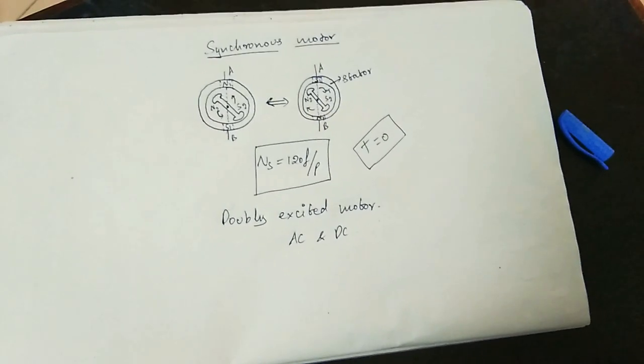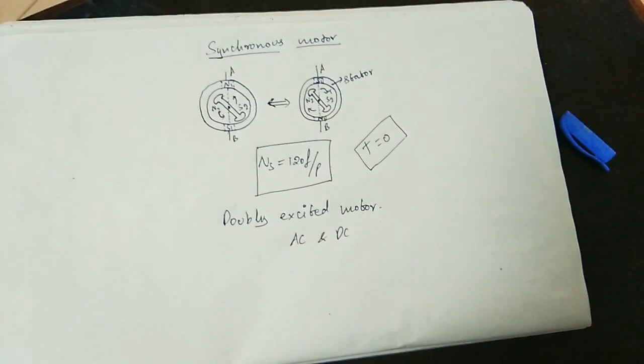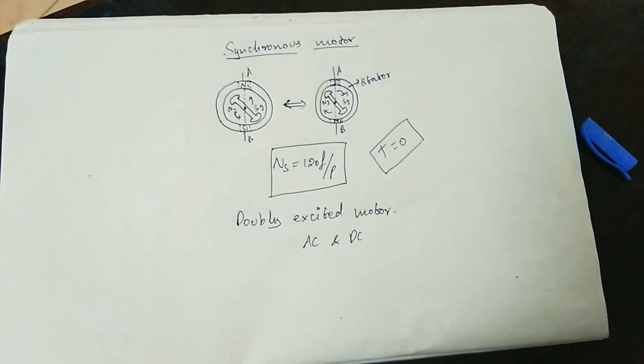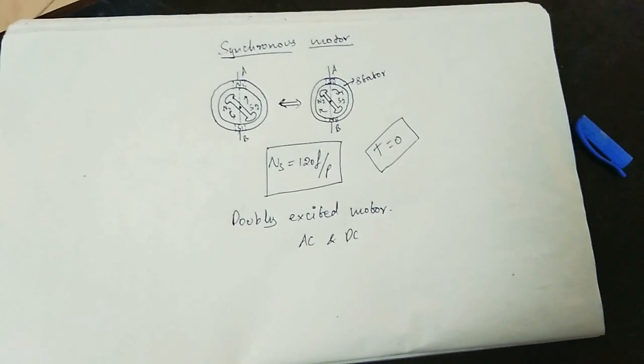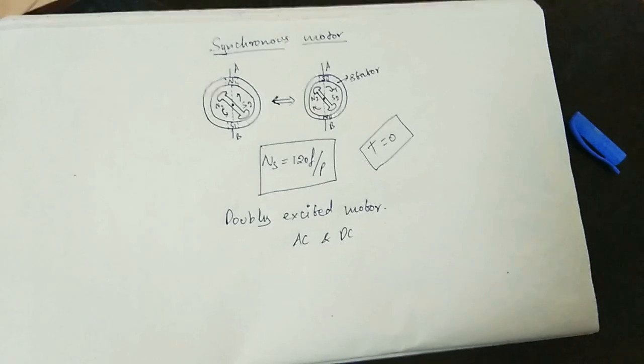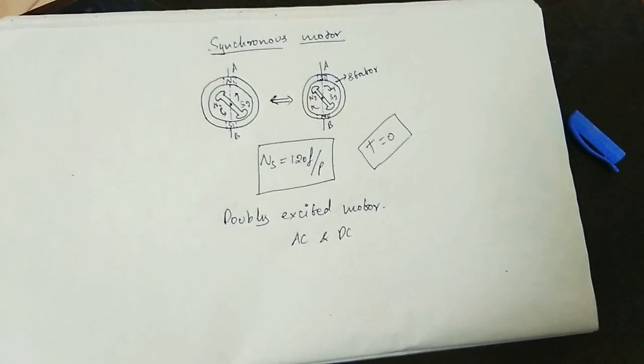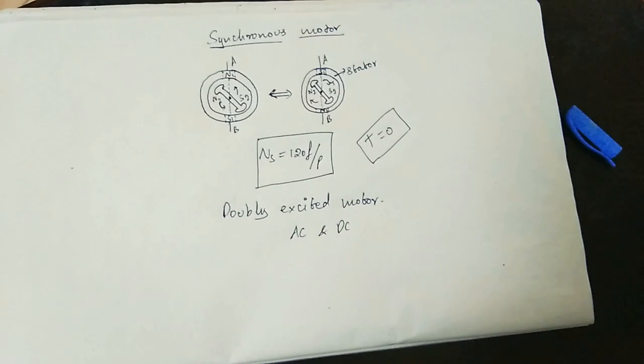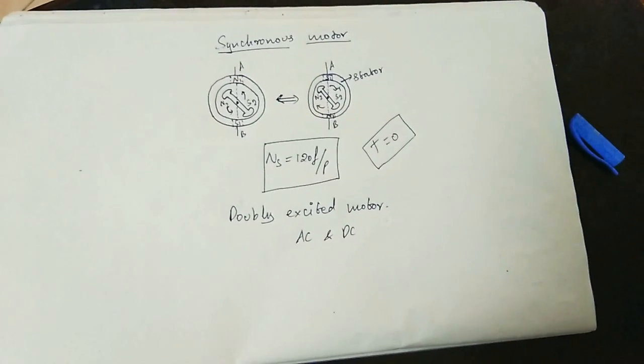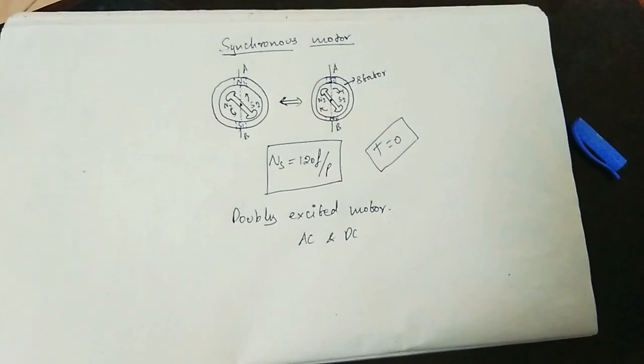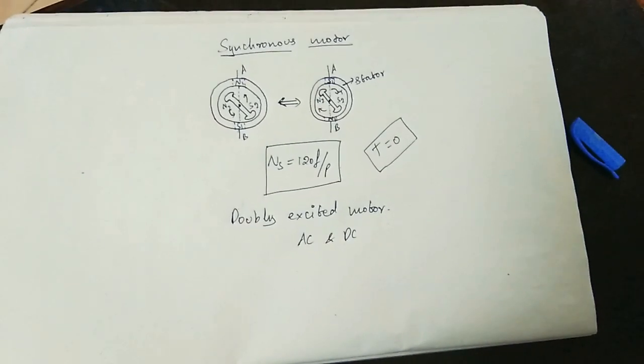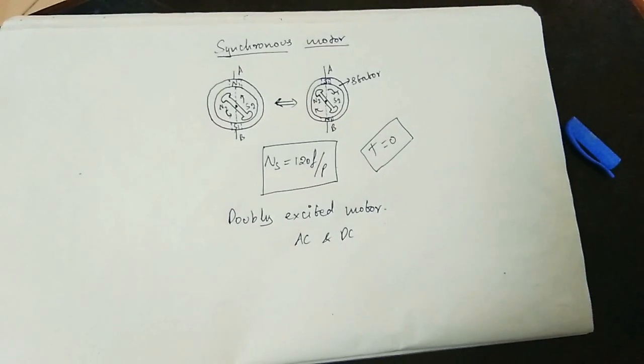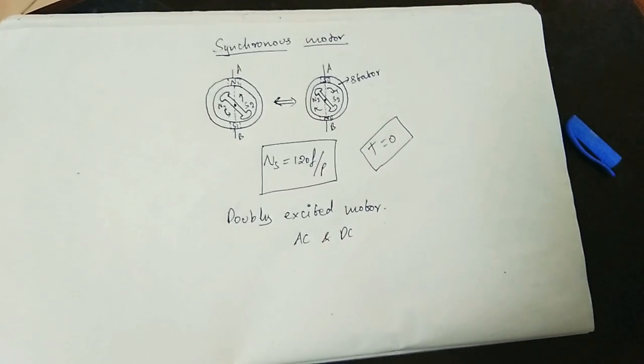The synchronous speed formula is N equals 120F over P. When we start the synchronous motor, there are many starting methods. For example, we can use an external rotating motor to bring the rotor up to synchronous speed before magnetic locking occurs.